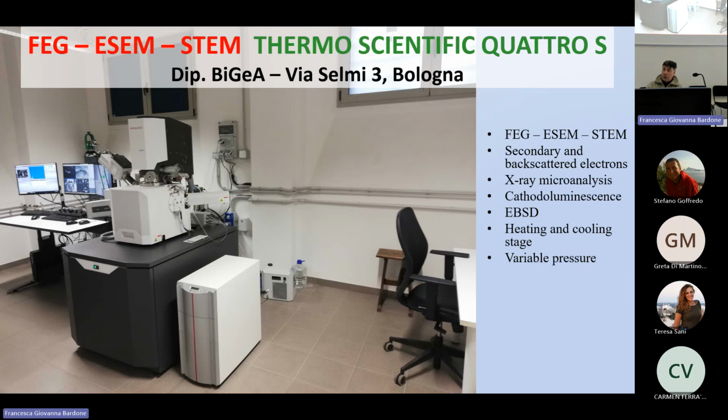If some of you already work with a classical scanning electron microscope, probably you remember that many techniques, many specimen preparation methods, require you to cover your sample with gold or carbon to create a conductive layer. Why? Because remember, you are using electrons to observe.